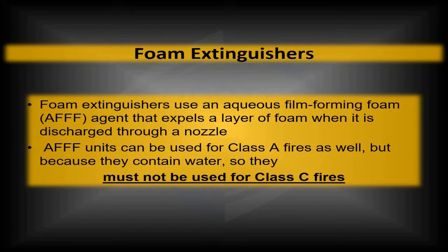When it comes to foam fire extinguishers, they are a little bit different. Just a second ago I said you cannot use water-style fire extinguishers to put out a Class B fire — meaning the pump style used on Class A fires. However, the AFFF fire extinguishers, which stands for aqueous film forming foam fire extinguishers, create a foam and are water-based. That water-based foam spreads and covers the fire area, stifling the oxygen. It's just a different way to do it. But because they are water-based, this makes it so that they cannot be used for Class C fires.